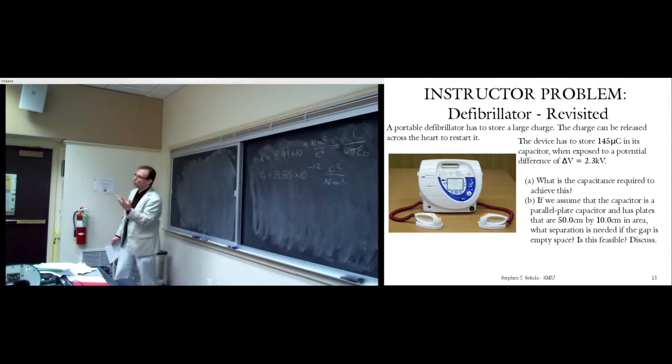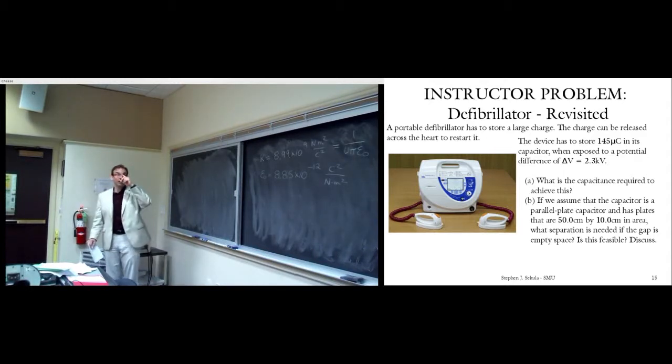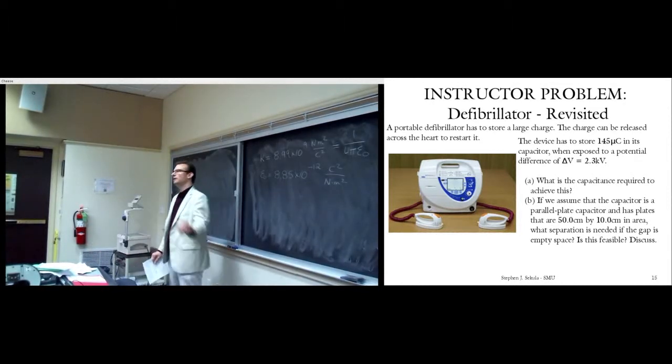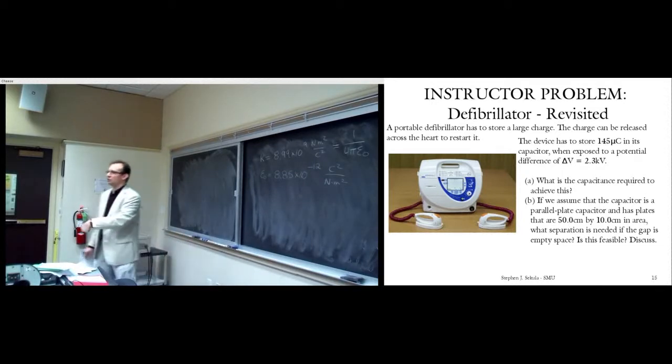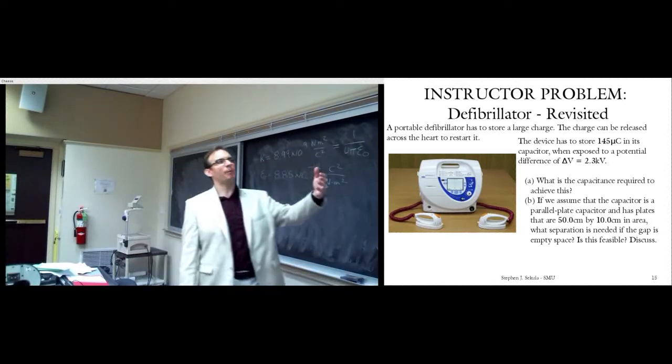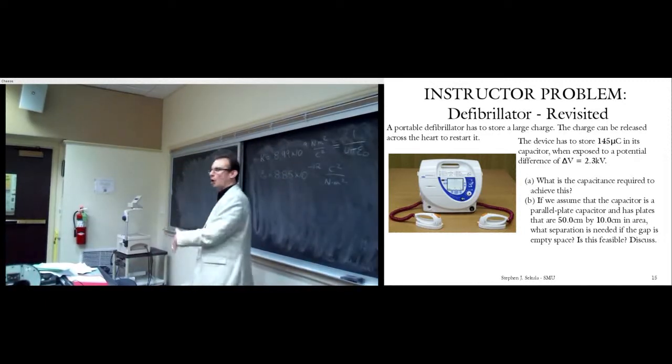What they do, okay, because you don't have to have the portable defibrillator plugged in when you charge up the paddles and say clear, okay, you can plug it in and charge it and then carry it around with you. All right, so you know, EMTs might do that. They might just have this in a case that they can carry with them. They could charge it up once back at the station and then drive around with it until they need to use it and then plug it in again when they're done, okay? To make that possible, this device must be capable of storing charge for long periods of time.